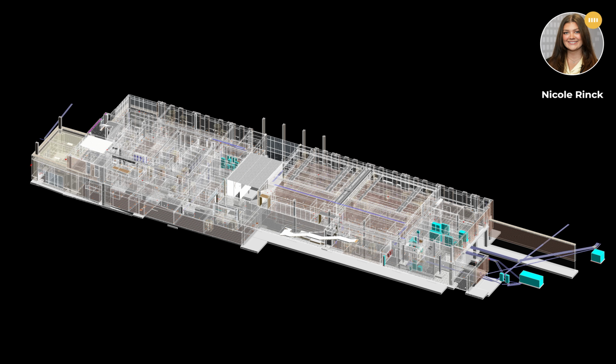From the branch panel boards, conduit and wire, shown in lavender, are run to various devices in the building to provide power. Mechanical, piping, and other equipment will need to be powered. It is important to coordinate the equipment requirements with the mechanical engineer and piping engineer to make sure the wire and circuit breakers are sized correctly.